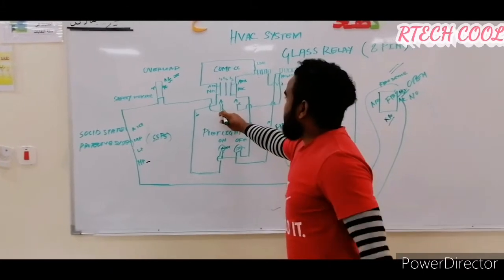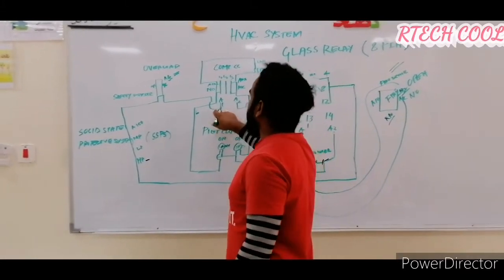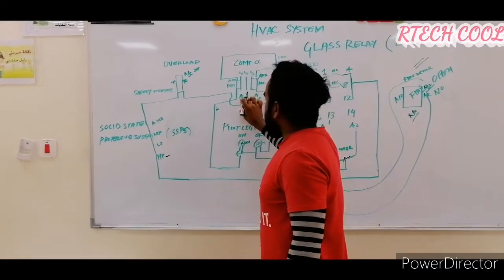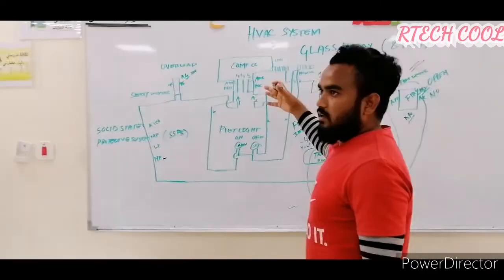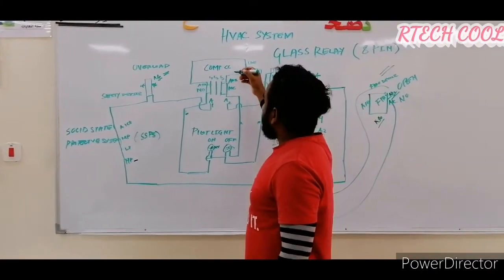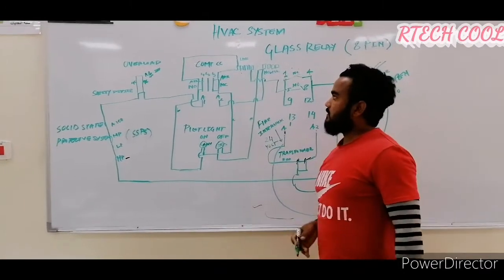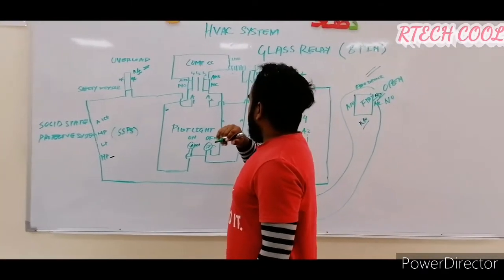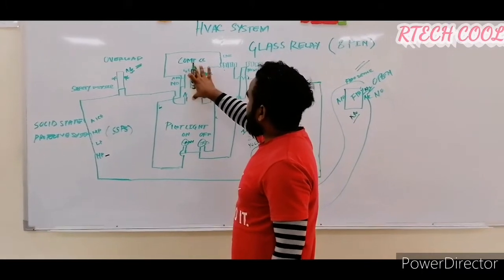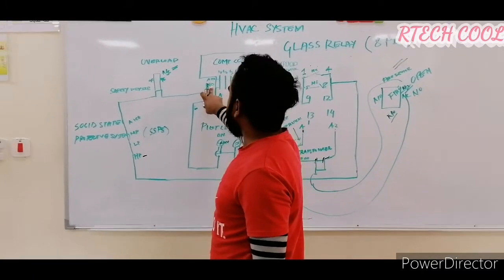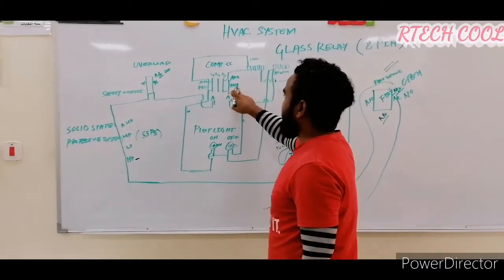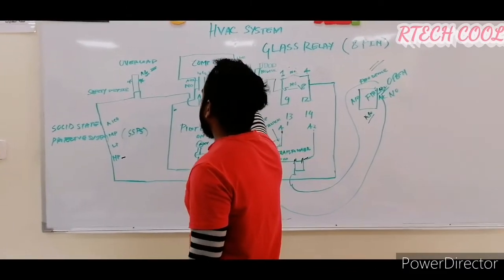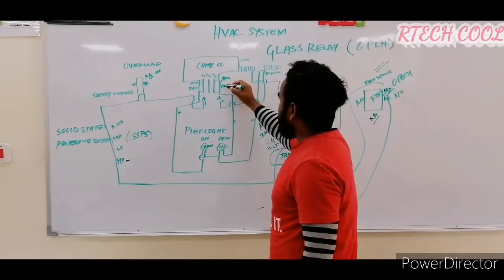The signal comes to the contact voltage — A1 of the compressor contactor — as the command or demand voltage. If this arrives, it will energize the compressor contactor. In the compressor contactor, we use auxiliary contacts — NO point and NC point. When the contactor is energized, this NO will become NC, and NC will become NO. Whenever a contactor or relay coil is energized, NC becomes NO and NO becomes NC.